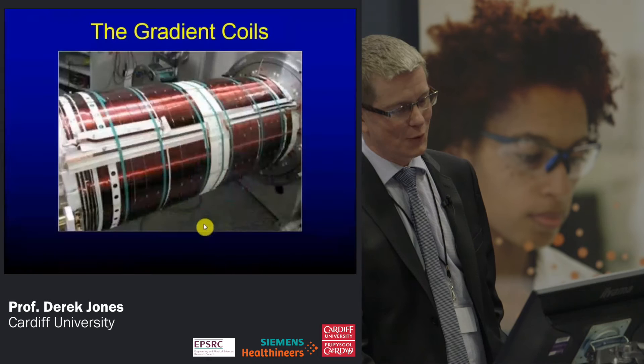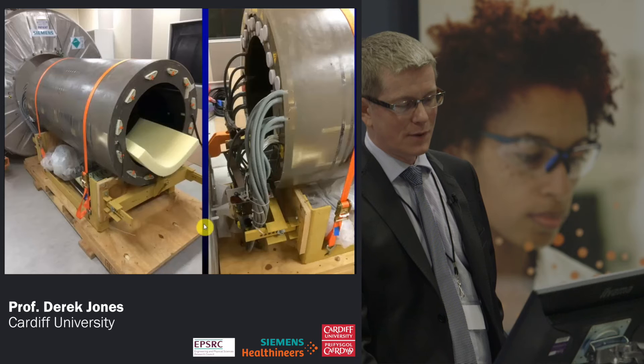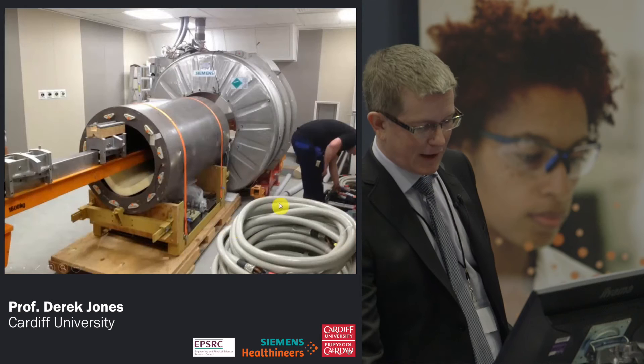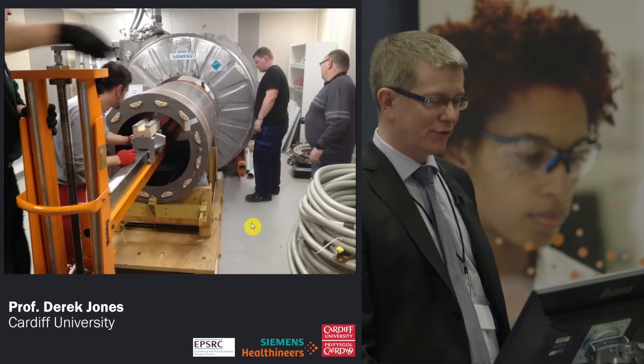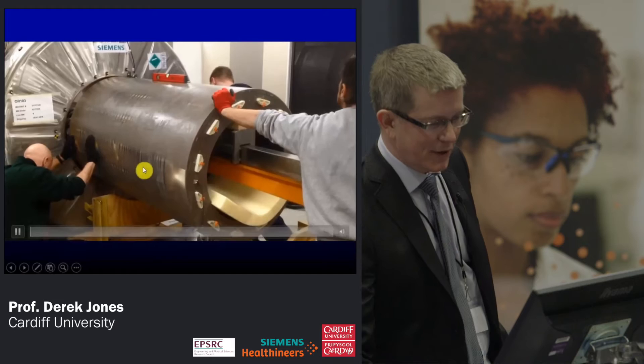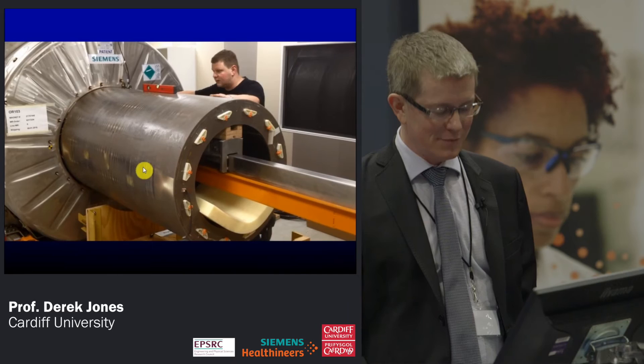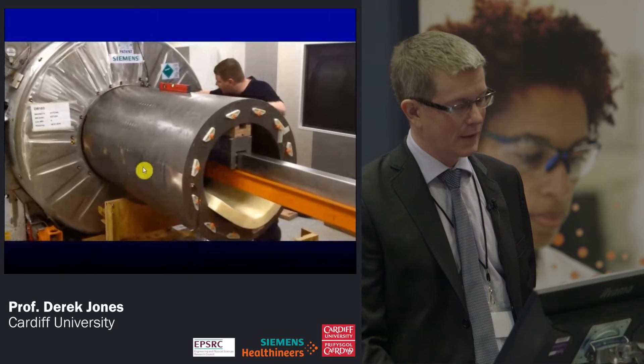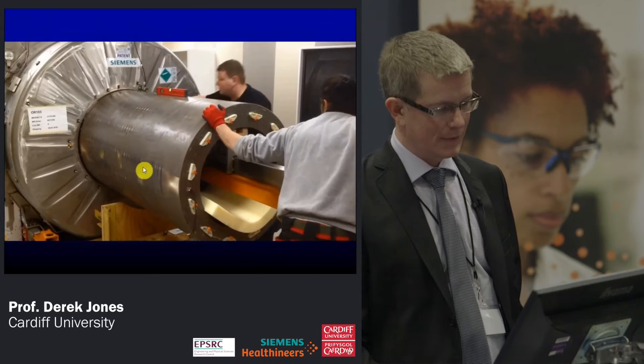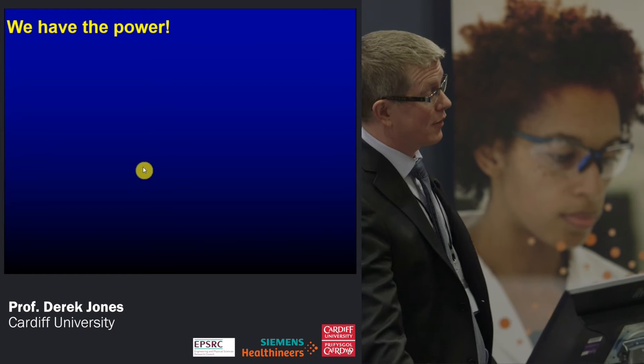This is not photoshopped — a pot of gold at the end of our rainbow. The Connectome was installed. Just to show you our little history: this was the arrival of the insert, which weighed about 1.5 tons. This is where the chilled water would go in and you can see the power cables — pretty beefy. We watched these guys put the insert in; it had to be correct within about a millimeter. You can see in this video just how carefully they check with the spirit level to make sure it's exactly right.